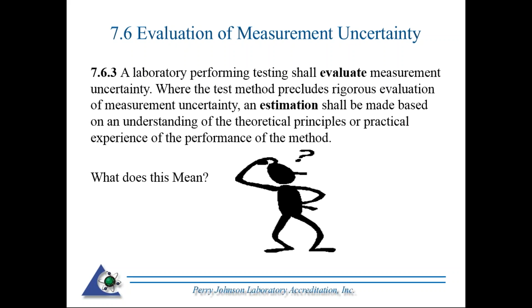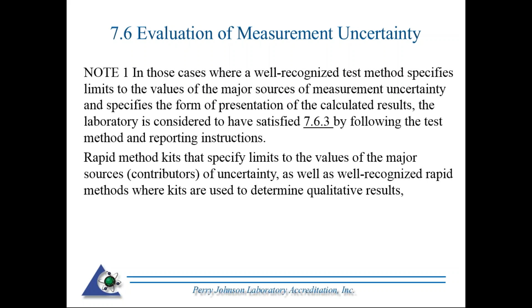So if we look at the standard, there's some additional information that the standard provides us in the case of notes. So note 1, in the cases where a well-recognized test method specifies limits to the value of the major sources of measurement uncertainty and specifies the form of presentation of the calculated results, the laboratory is considered to have satisfied clause 7.6.3 by following the test methods and reporting instructions. An example could be, for instance, rapid method kits that specify limits to the values of the major sources, i.e. contributors of uncertainty, as well as well-recognized rapid methods where kits are used to determine qualitative results. Perhaps your testing lab falls within this bucket.